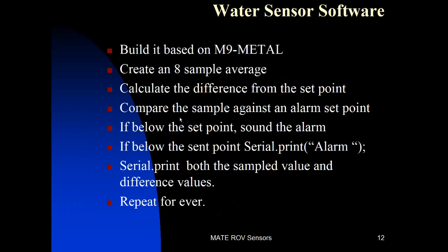So as far as the software, copy M9 metal and do a save as M9-water. You'll create an 8 sample average. You'll calculate the difference from a set point. I put 1000 as my set point, or my alarm set point. Anything below 1000 would sound an alarm.